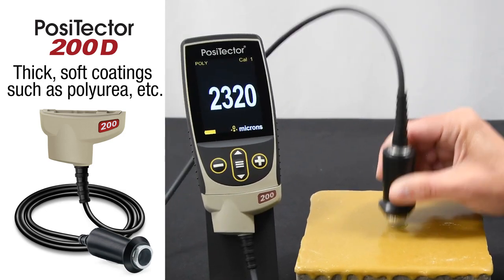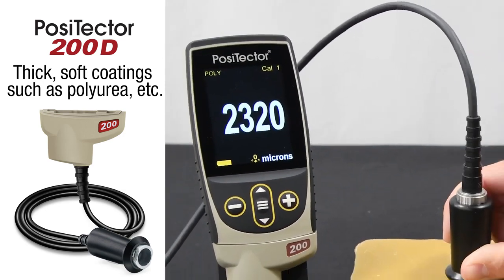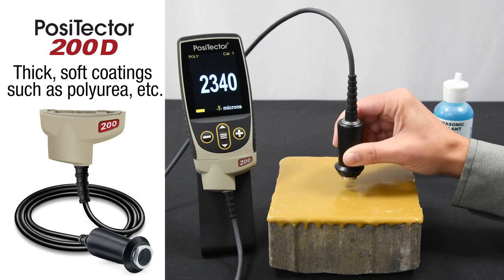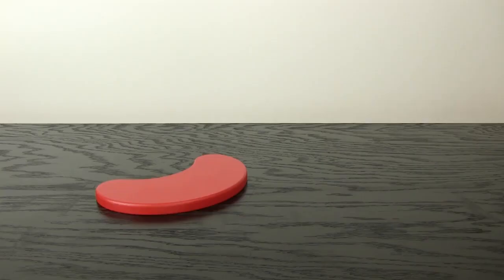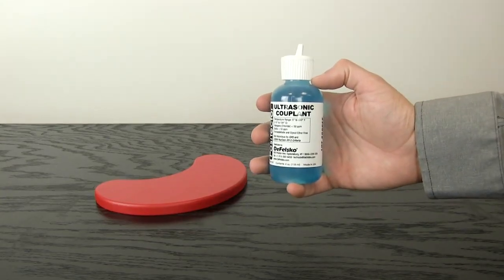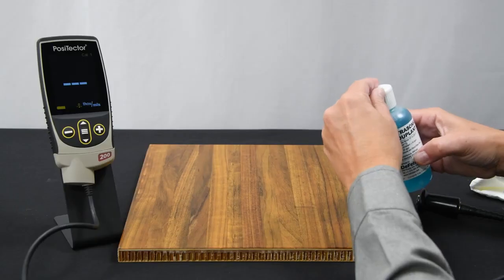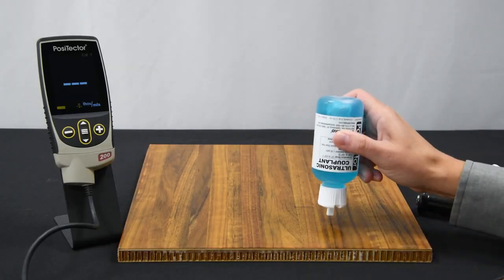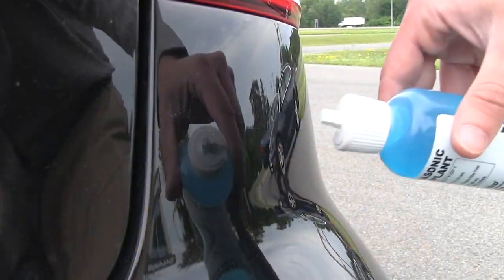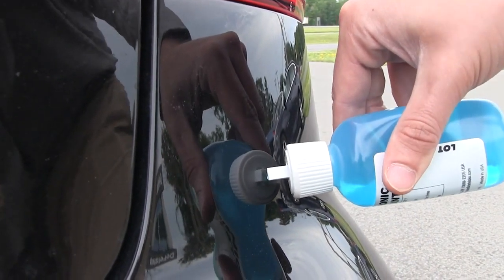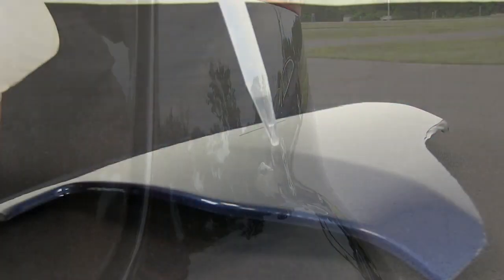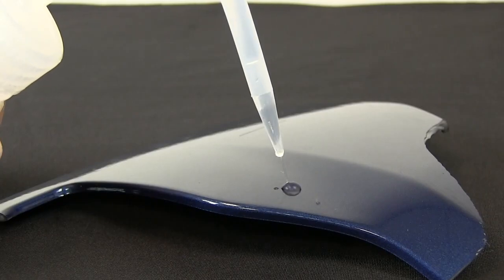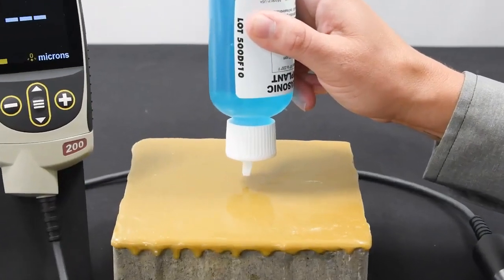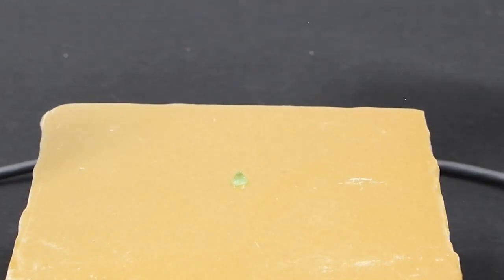With polyurea mode selected, the gauge loads a pre-programmed mode optimized for polyurea measurement. For all measurements, couplant is required to help propagate ultrasound into the coating. The included gel is ideal for rough coatings and for vertical surfaces. Alternatively, a drop of water is often sufficient for smooth coatings on horizontal surfaces. Only a small pea-sized drop is necessary.